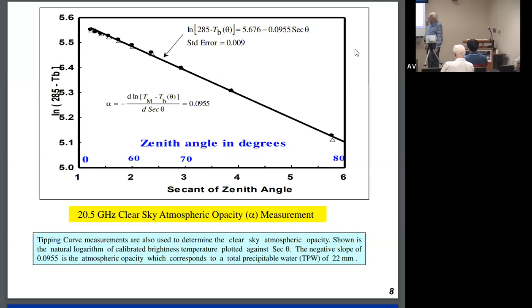There are three ways. There is the tipping curve I just mentioned. And then there's also a method where they use liquid nitrogen. Liquid nitrogen is tough to work with, but people like it because it's the coldest laboratory measurement you can get. They look at the liquid nitrogen with the antenna to measure the lowest possible temperature that they can get easily. And then, of course, you've got your second calibration point, which is just your ambient, the warm target. That's the method that people sometimes use. Okay, that's the second method.